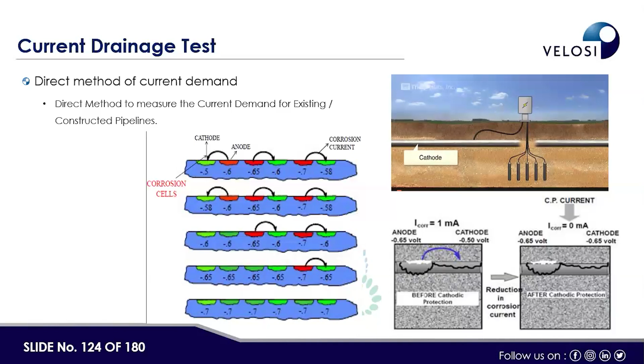So with this natural potential survey, we then slowly apply current, starting with 2 ampere, and see how the potential changes at that location. The moment the anode and cathode potentials are minimized, that indicates the current required. Or we use the NACE criterion of 850 millivolt. If we measure at every location after applying the temporary CP system and get 850 millivolt, we can then measure how much current is required. For example, one contractor already installed a pipeline, and we measured the potential, which is less than 850 millivolt. So he keeps applying current until he achieves a minimum of 850 millivolt wherever we measure. That we call the current drain test.